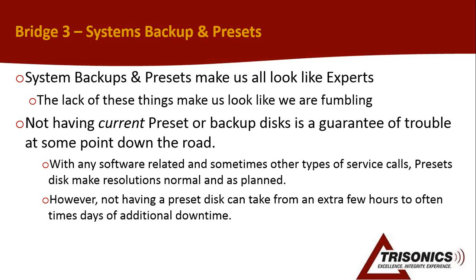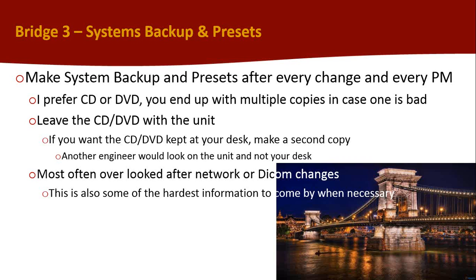And I've had it run. I had a hospital situation probably about 1.5 years ago where this occurred, and we had everything but the unit's IP address. And it was a particularly special situation, and only one person had that IP address, and that person was on vacation. And we literally had to wait for 3 days for that to come back. So even though the unit was fully up and running the same day that they placed the service call, they weren't able to use that unit for 3 days because there was no IP address and we couldn't send the images. So system backups and presets are so important to do.